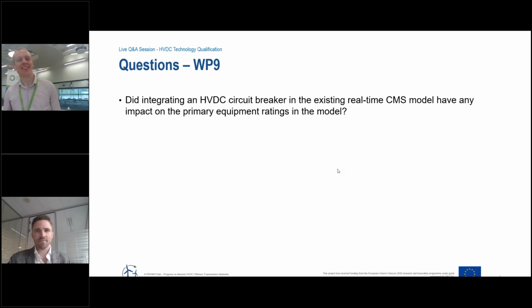Yeah, so there are several different ways that we measure the system performance. In addition to measuring the performance of the protection IEDs as a standalone performance, looking at the operation time of the IED, we use key performance indicators to look at the overall system performance, and this includes real power recovery time and reactive power recovery time.